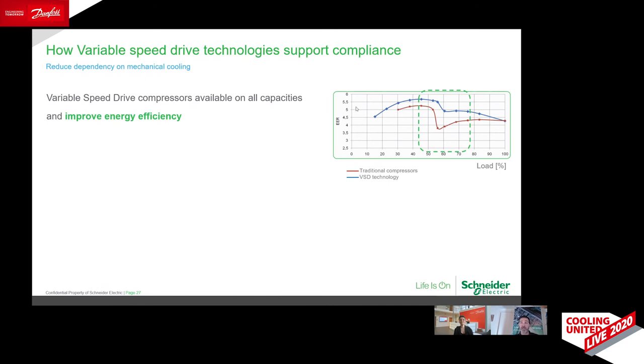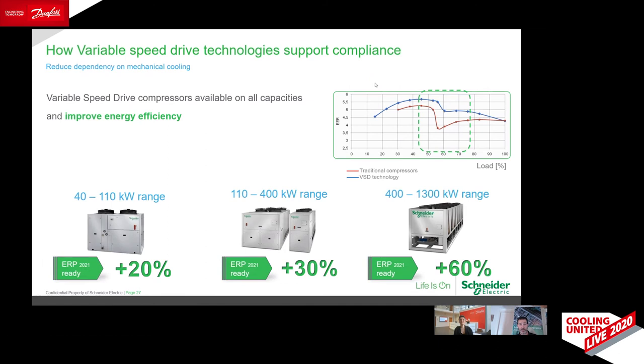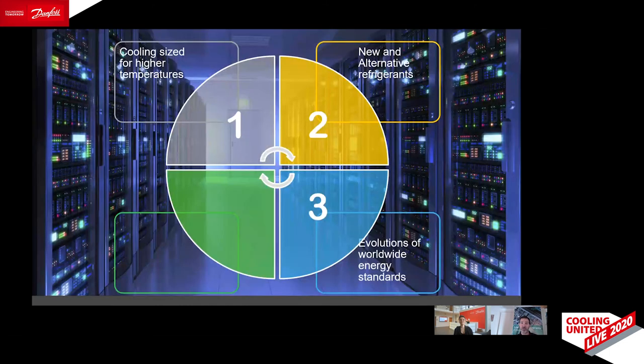And when we look at the diagram there, the place where variable speed is better than the traditional compressors is at part load condition. And definitely this helps in getting more and more efficiency. And certainly when we look at the product range we have, the range with inverter is already suitable for the Ecodesign 2021. So definitely, point number three of this classification is the energy standard.